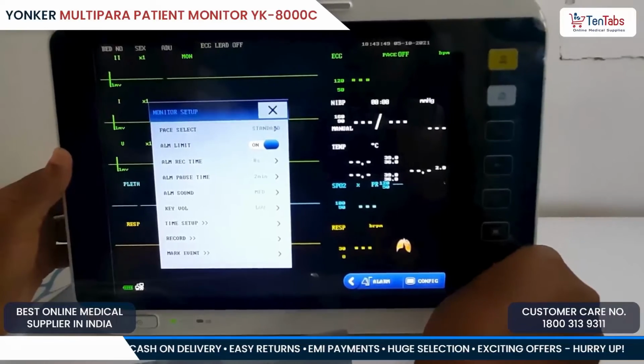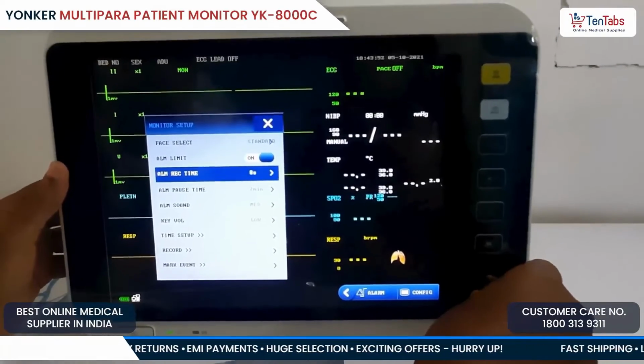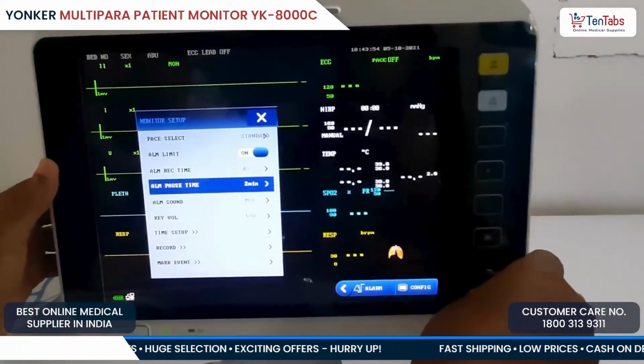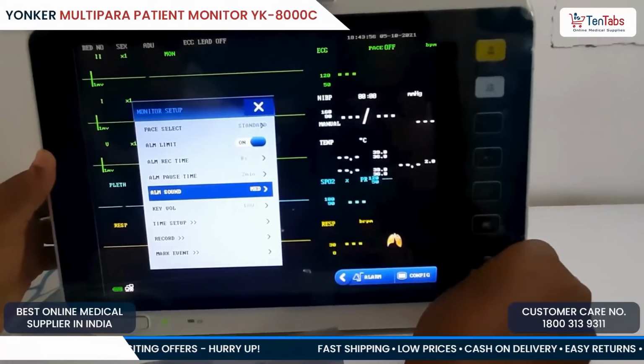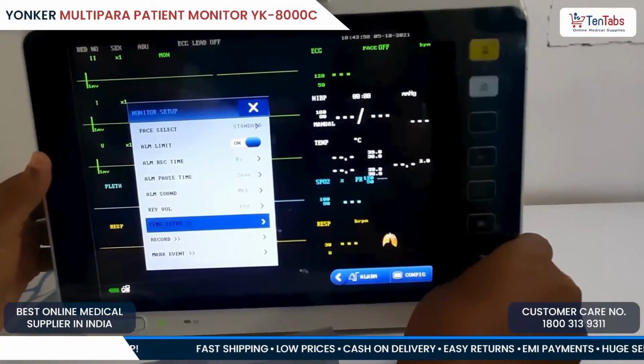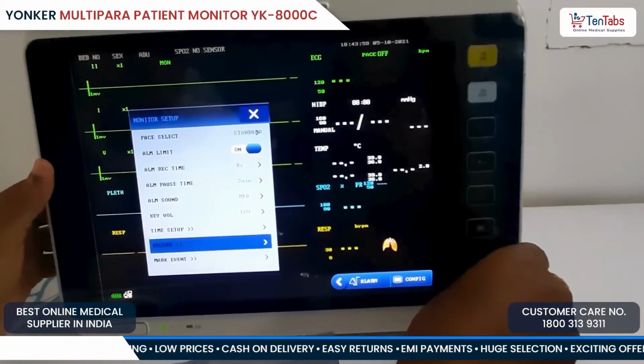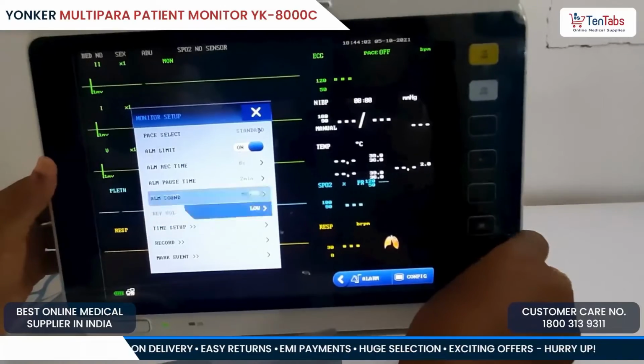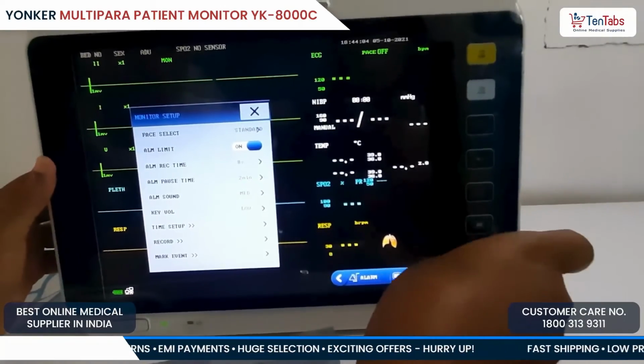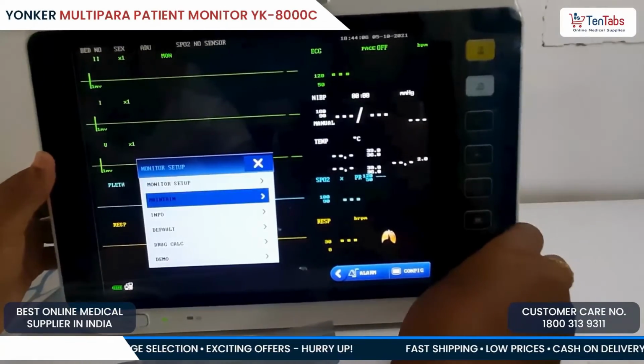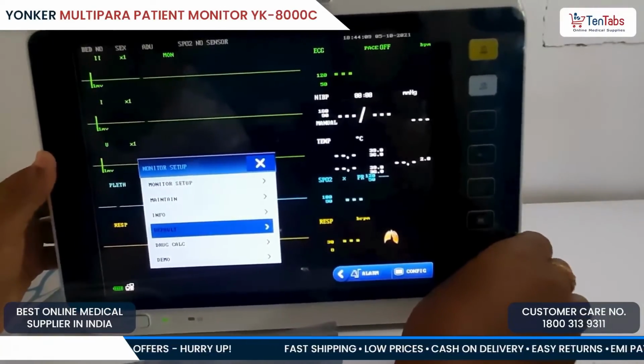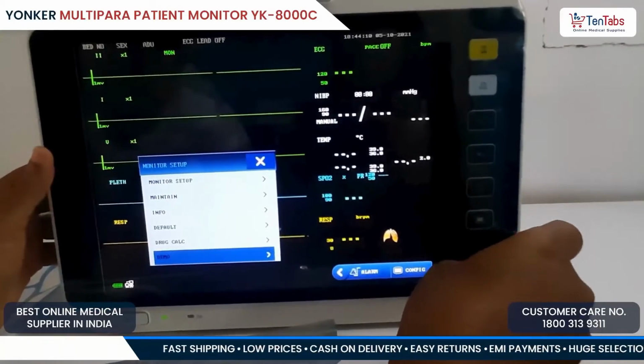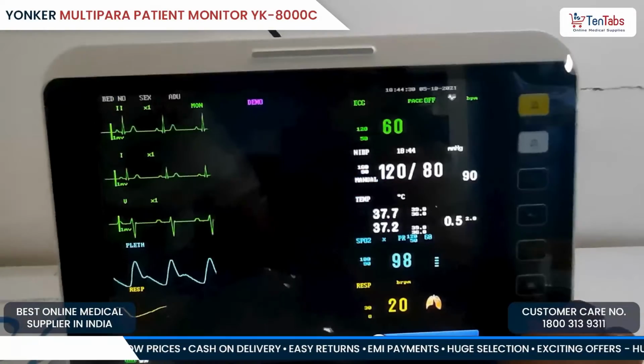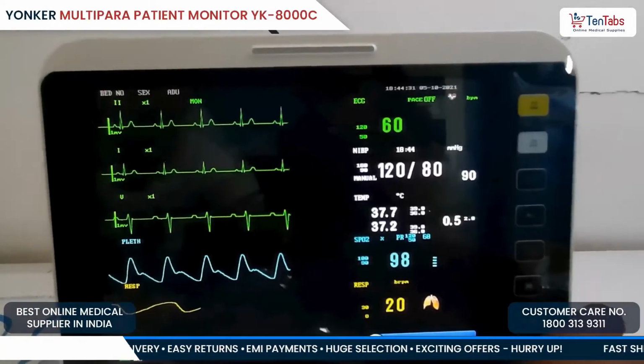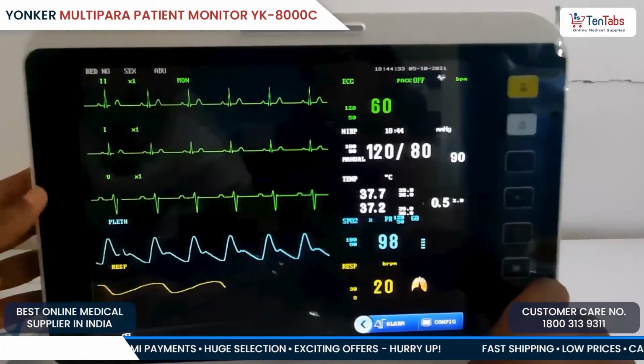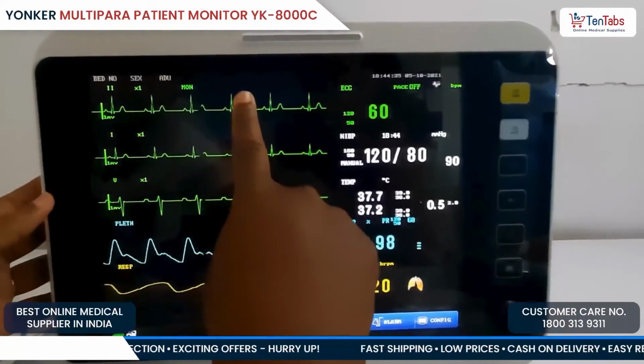And then you have some other settings, which are the alarm limit, the record time, alarm sound, key volumes, time setup, record and mark event. So this comes under the monitor setup. And then I will show you the demo mode. So now the monitor is in demo mode, as you see here.